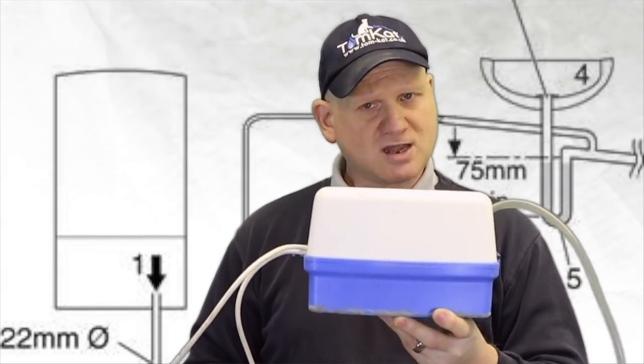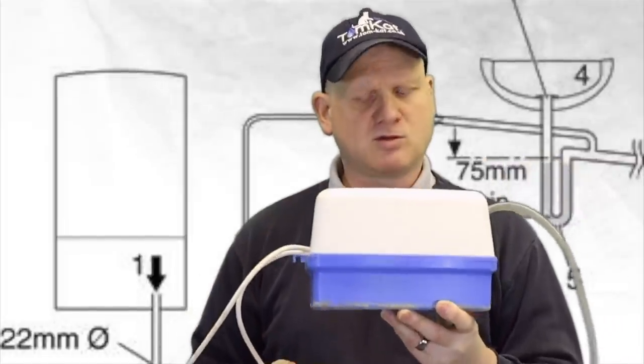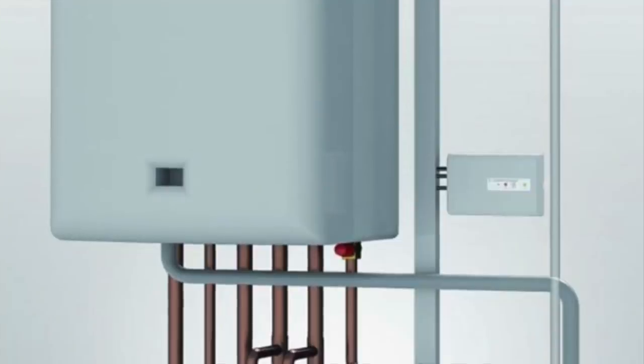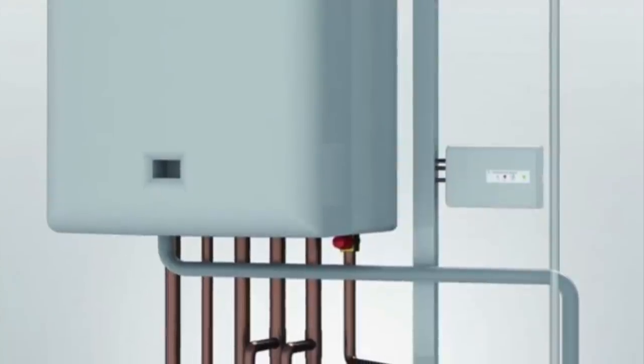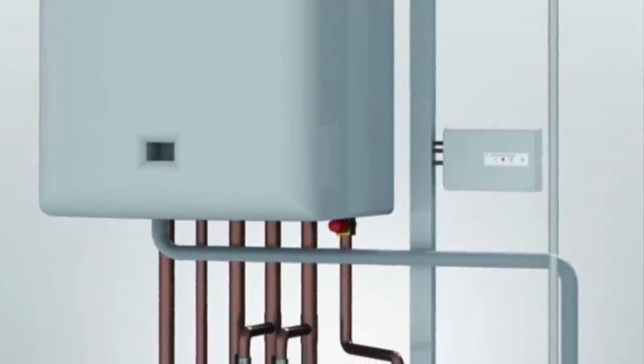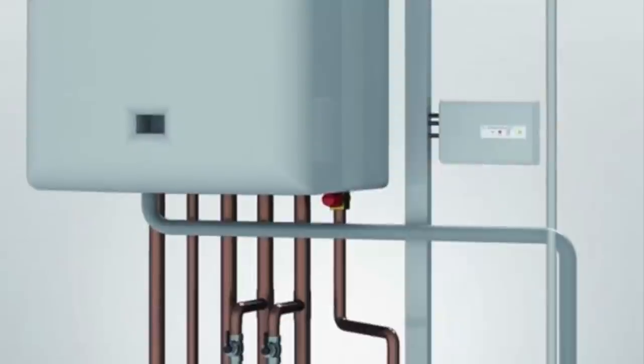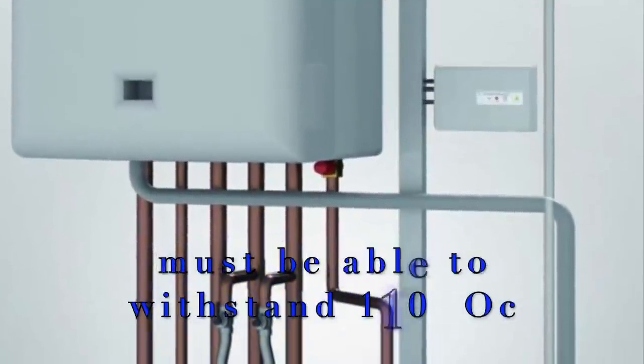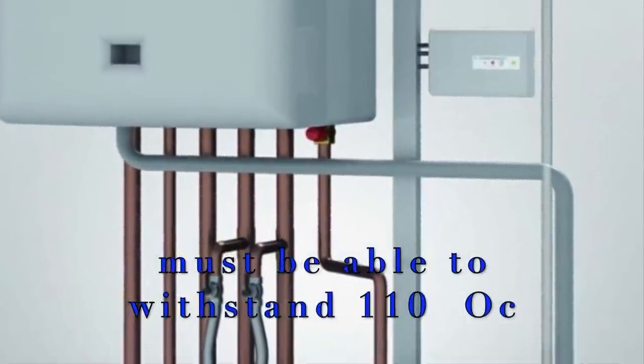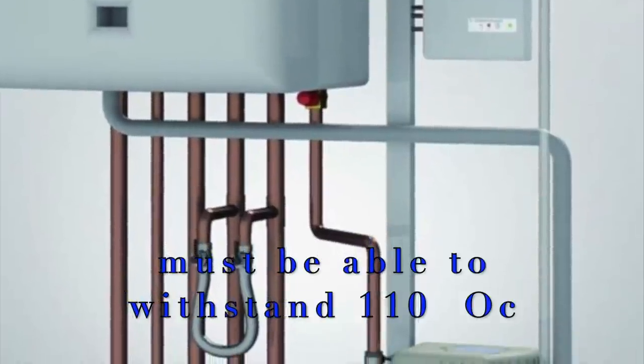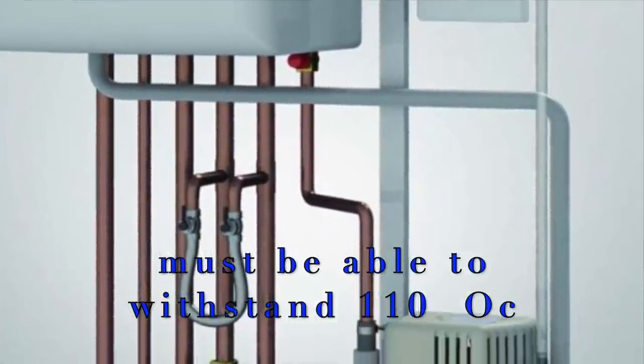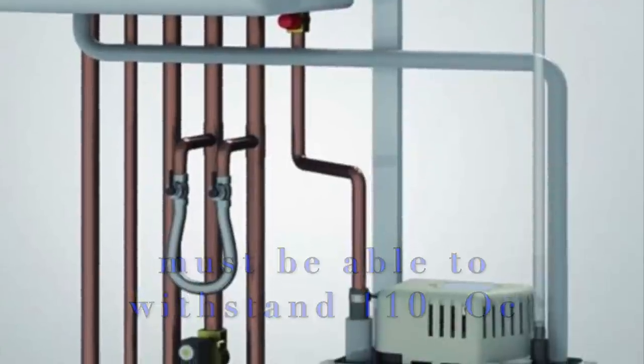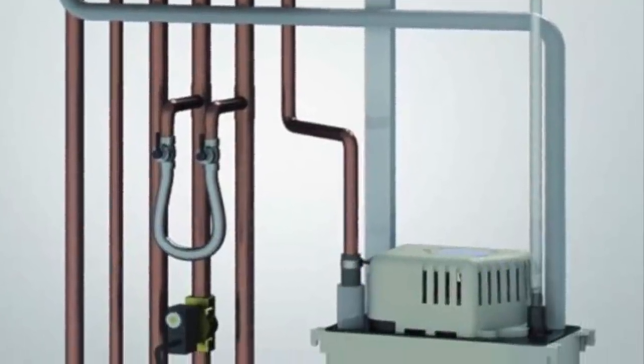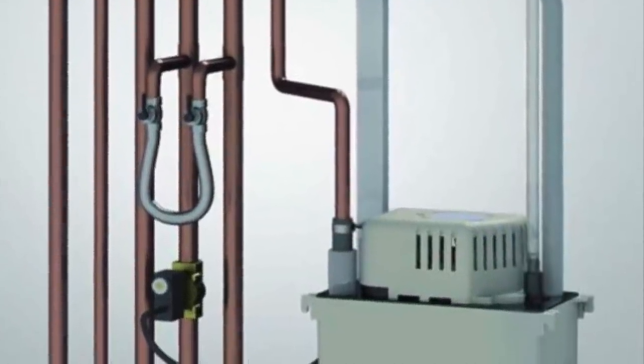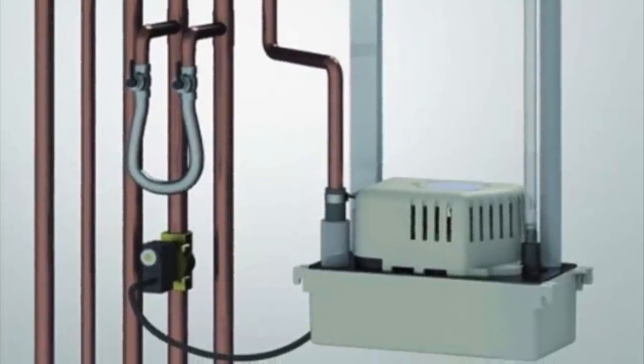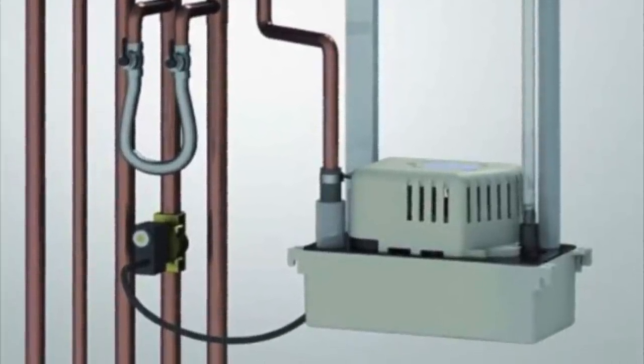So that's one way you can do it, which is a condensate pump. There are also some purpose-made condensate pumps where you can actually put your discharge pipe into them also. But you can't just use any condensate pump, you've got to use a specialised one, which will take the temperature of your discharge water also. So, it also helps when you're installing a boiler in a flat or a basement and the drains are above. You can actually put your discharge pipe in there also.